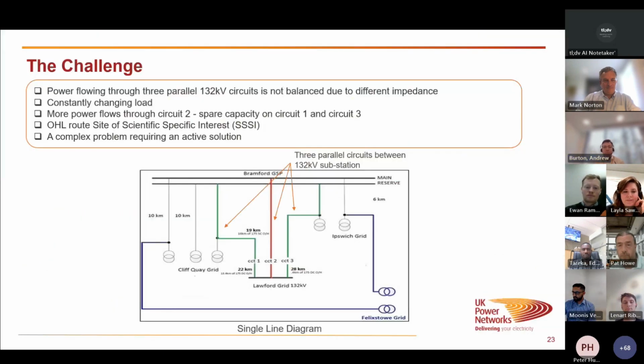Next slide, please. First we looked at what the challenge was. We had one circuit that was consistently going high, and it was causing problems on the network. When we investigated, we identified there were 3 circuits, all different lengths, and they weren't balanced properly. Circuit 2 was the shortest length, so the impedance was lower compared to the other 2.